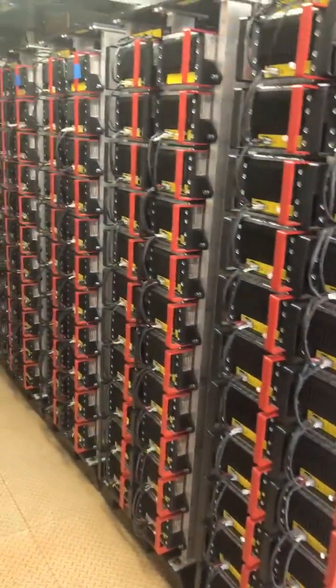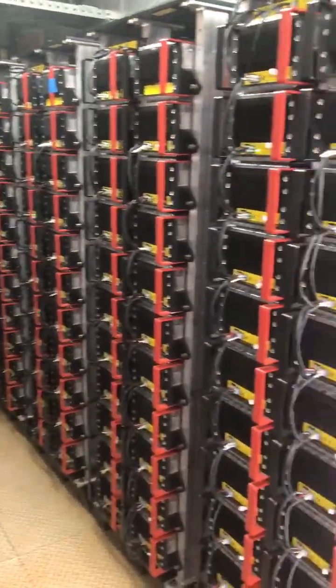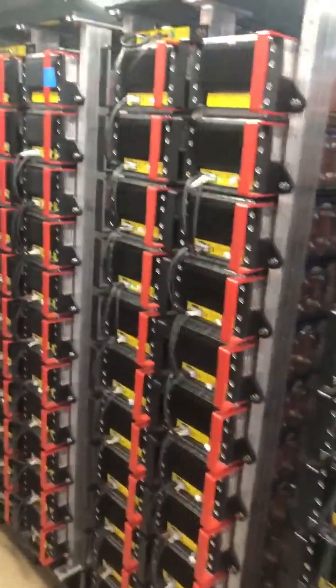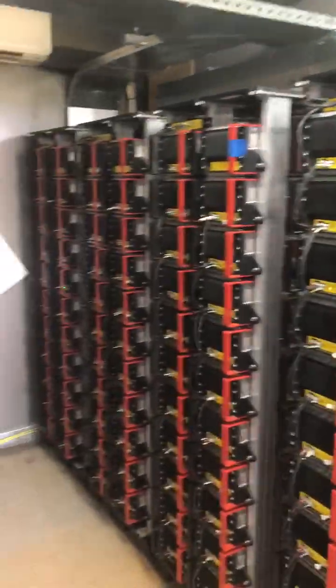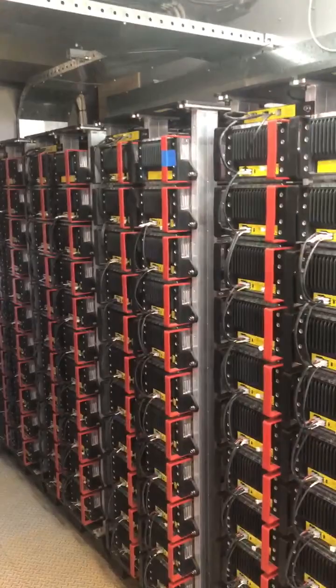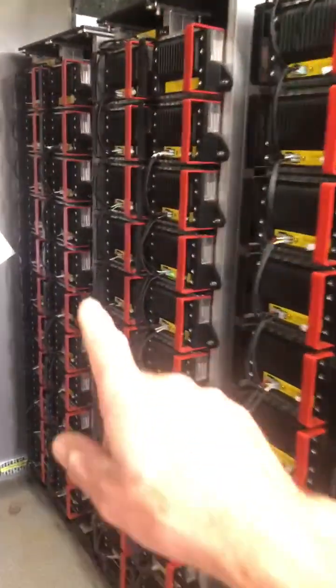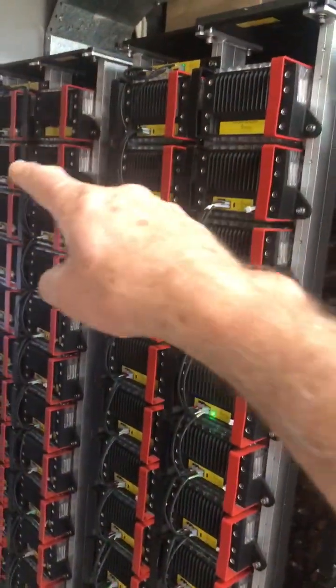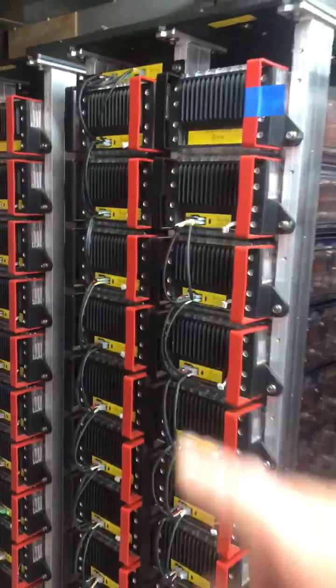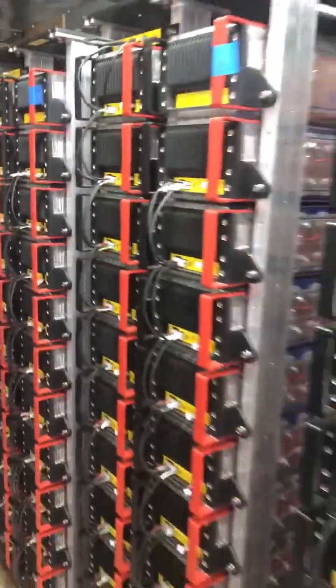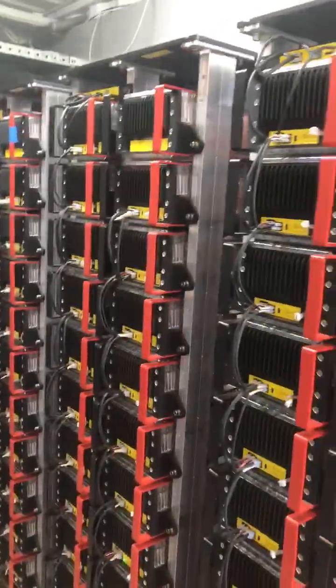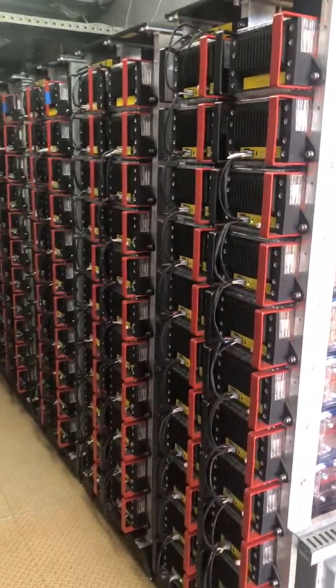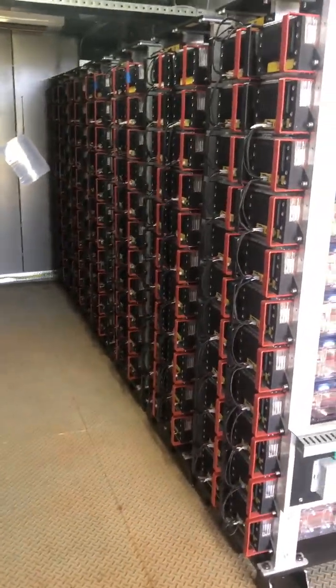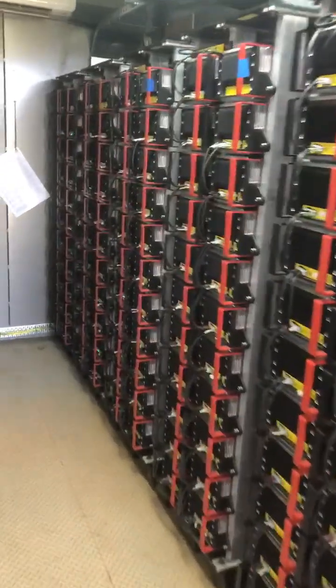If we look at these 6 batteries, remember I said that we needed to keep the battery cables the same length. So if we had just brought all the cables to the first 3 stacks, there's 1 stack, 2 stack, 3 stack, and then we'd wire the other string in number 4, 5 and 6 stack, the battery cables would have been considerably different in length.